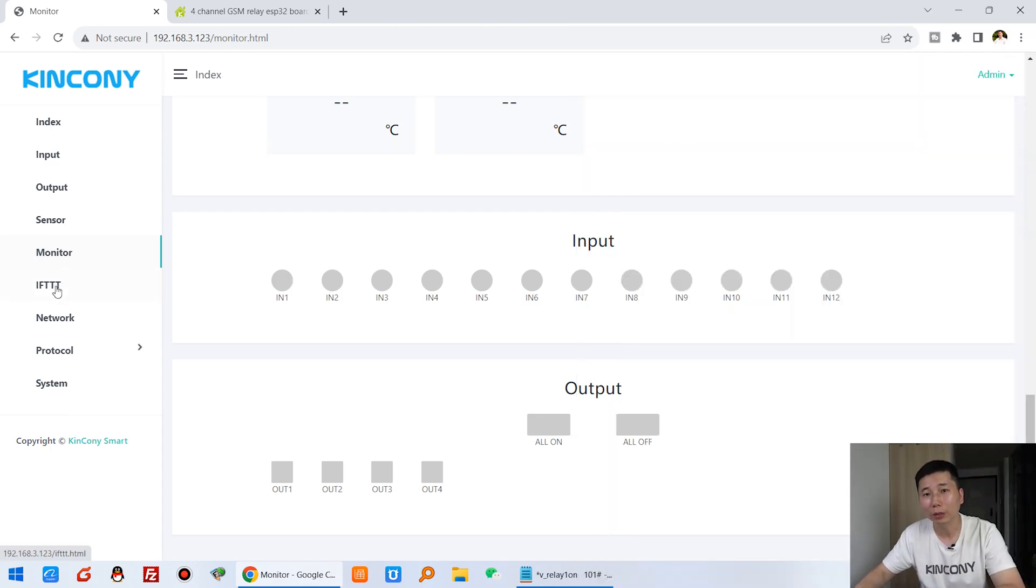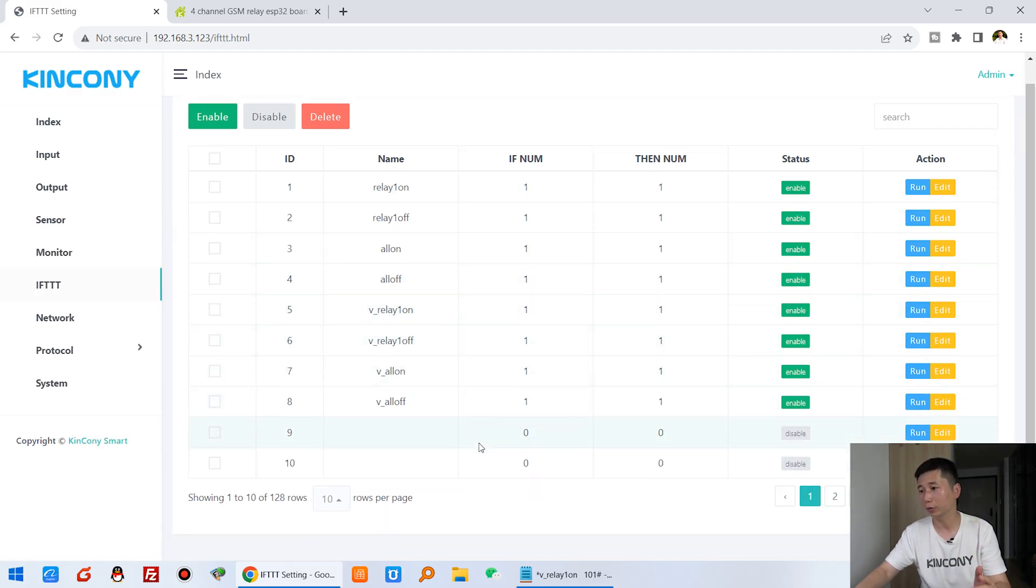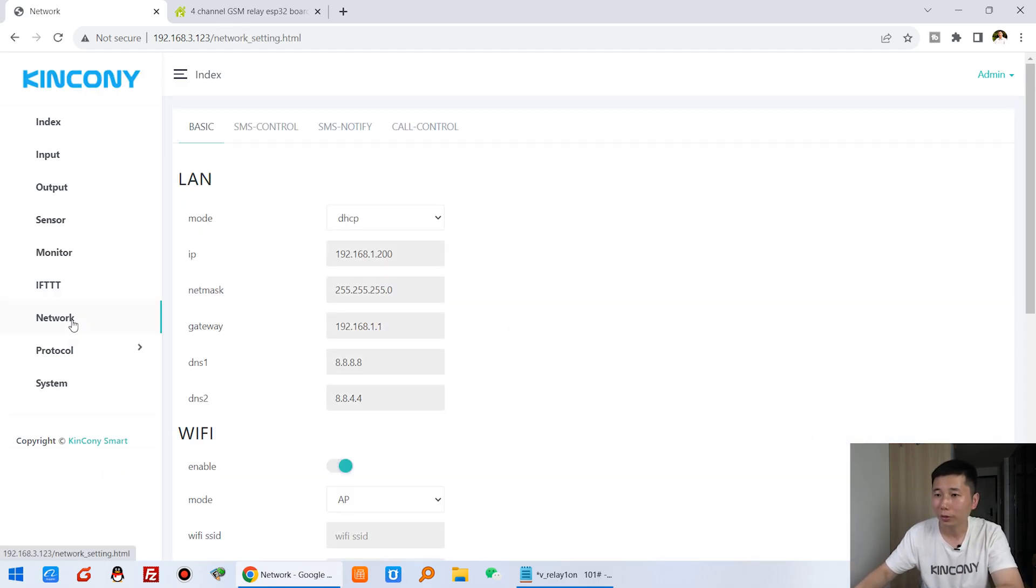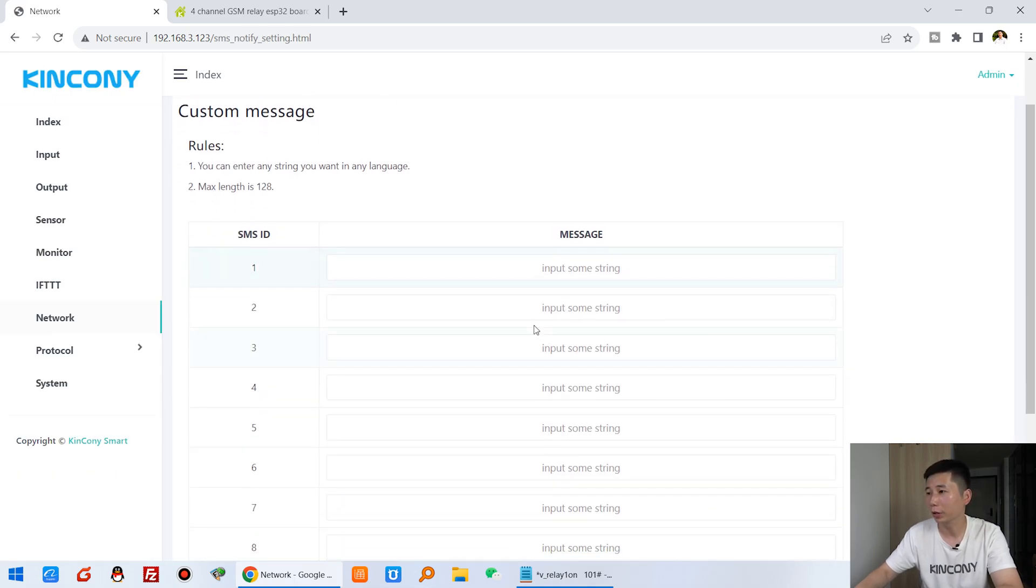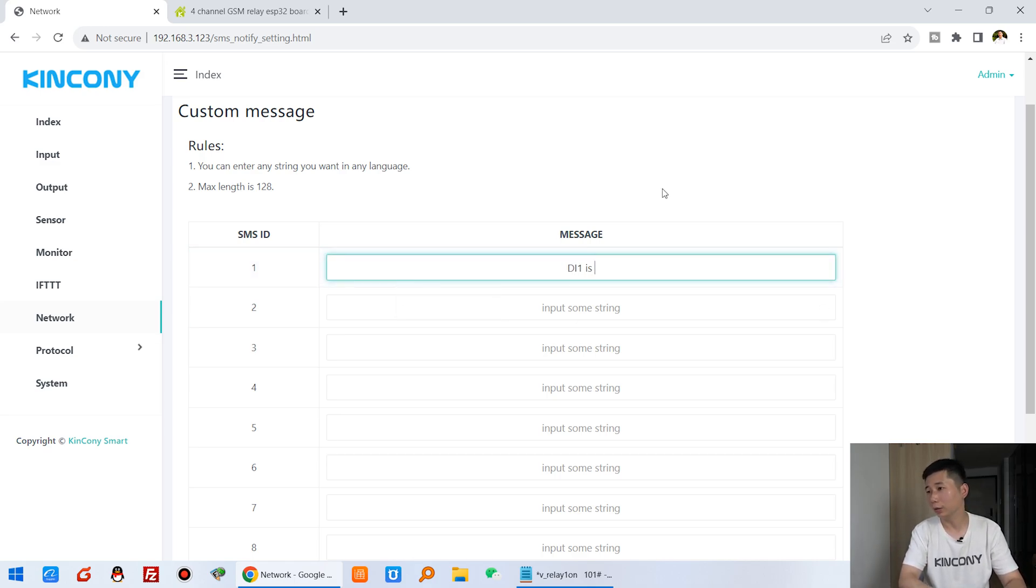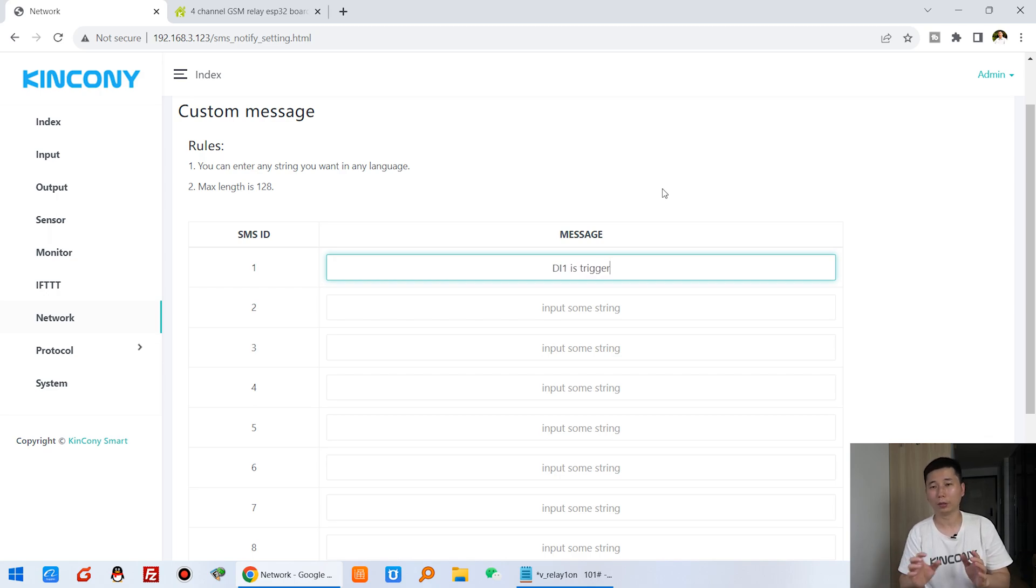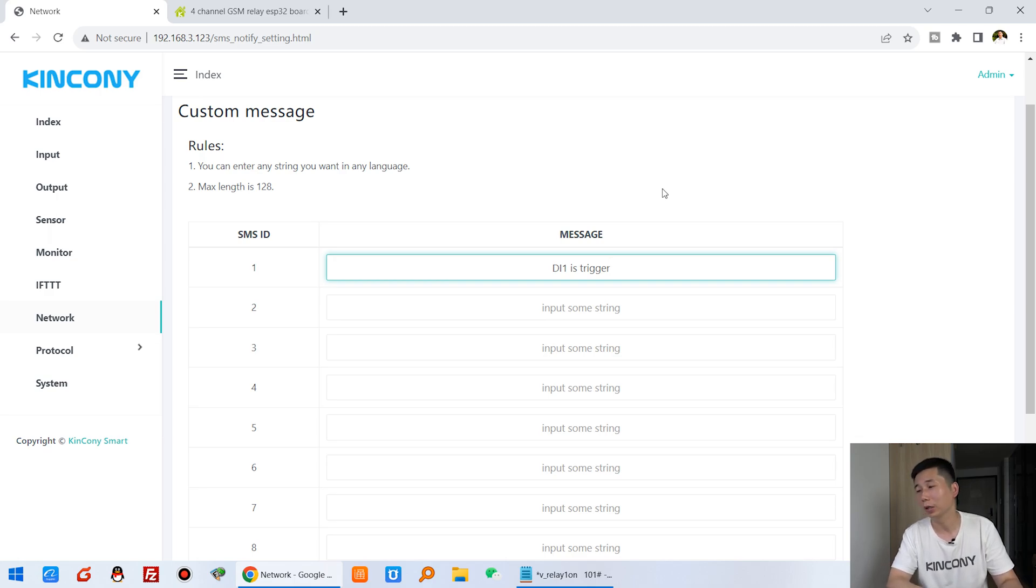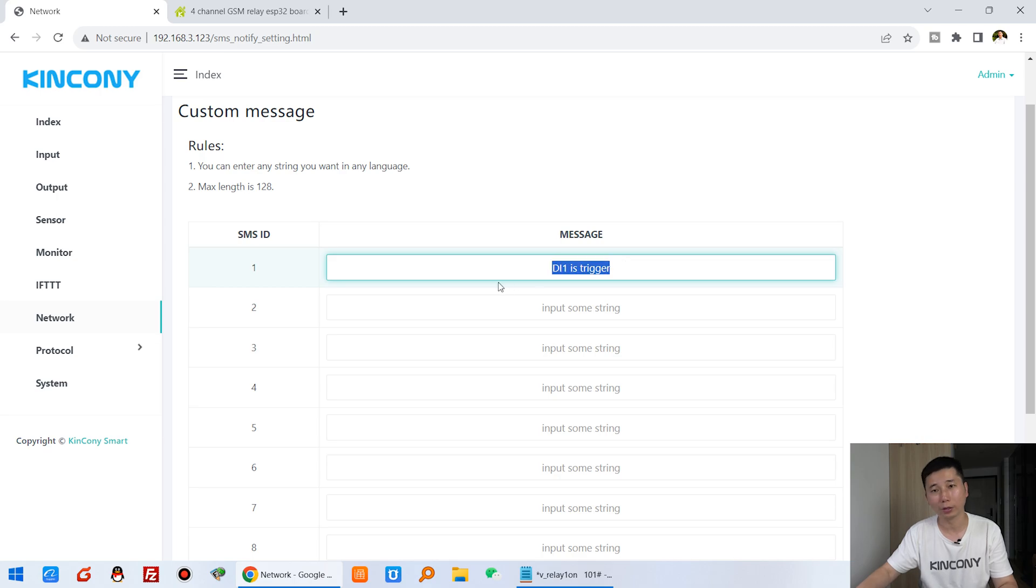We can go to this IFTTT command. And this time I want to use this digital input 1 triggered, then send a short message. So we can create this short message. You can see short message notification. We can create this message number, so that DI1 is triggered. Maybe you can connect with the door sensor. You can input the door is open or the door is closed. Also you can input your native language such as English, Chinese, Japanese, Russian, and Korean. Any language will be supported, sent by the short message. We can click save.